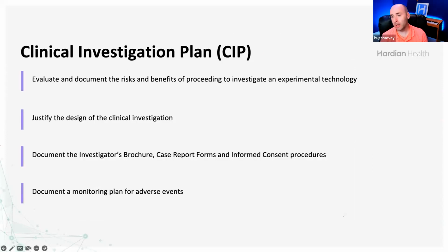So there is some documentation. So going back to that question about what documentation do you need to present, this is one of them. It's called a CIP, a clinical investigation plan. You might recognize this as a clinical trial protocol. Obviously, as I said at the very start, we don't use the term trial in medical devices, we use investigation. So it's a CIP. But in essence, it is like writing down a formal protocol.